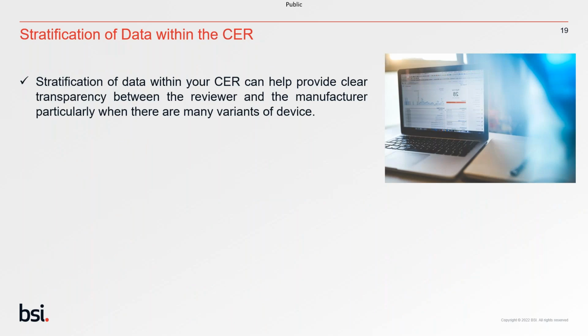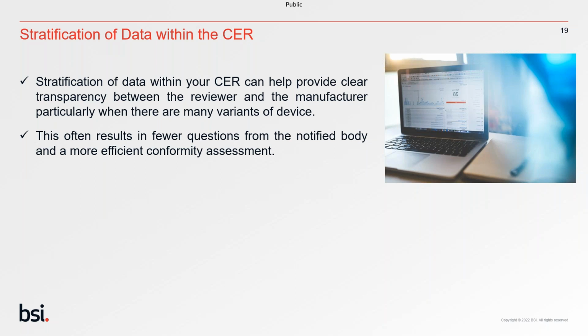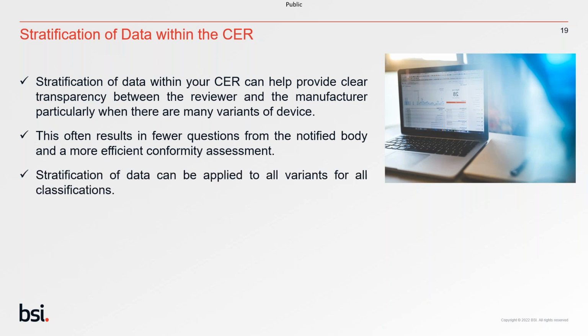So it also helps provide transparency between the reviewer and the manufacturer, particularly when there are many variants of device. So that's one of the benefits of it. This often results in fewer questions from the notified body, because we can instantly see, once you've stratified that data, where your gaps are and where you've addressed those in your PMCF plan. And even for you as a manufacturer, performing this exercise really does give you insight into the data you hold and where perhaps you need to perform specific or general PMCF activities to really come back and then solidify the data you hold across the range of devices that you have for all the indications.